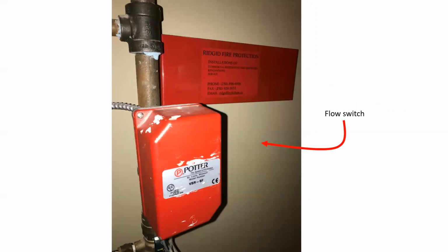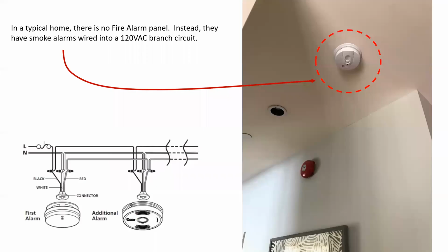Finally, we have the only electrical connection, which is a standard fire alarm 120 volt rated flow switch. Now the question comes up, what does the flow switch connect to? Well, in a typical home, there is no fire alarm panel. Instead, they have smoke alarms wired into a 120 volt AC branch circuit. Each of these is connected in parallel, and if one of them goes into alarm, they all go into alarm.